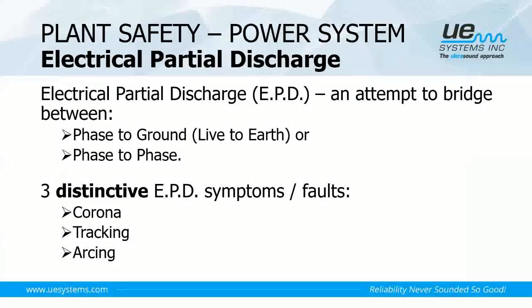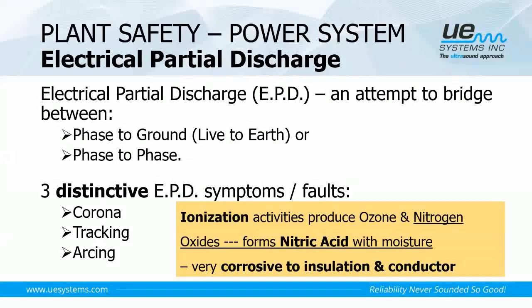Electrical partial discharge is an attempt to bridge between phase to ground or phase to phase. There are three distinctive electrical partial discharge symptoms: corona, tracking, and arcing. This activity will generate ionization, which produces ozone and nitrogen oxide. Nitrogen oxide will form nitric acid with moisture, and nitric acid is very corrosive to insulation and conductors.